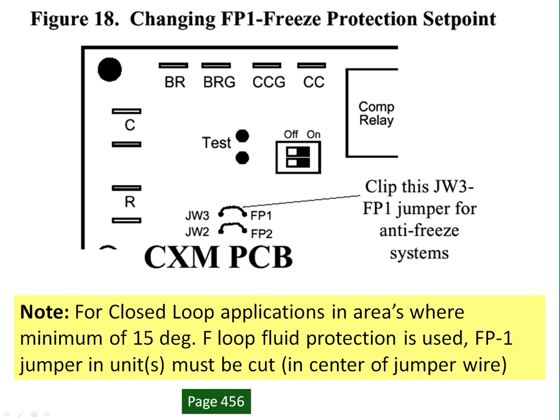So now you're good to go to cut that FP1 or JW3 jumper. What you want to do is make sure that when you cut that jumper, you separate those wires. I've seen guys just snip it, and yet the wires are close enough together they actually kind of remake contact. So make sure you separate them out a little bit, and please double check before and after you cut this jumper that you have cut the correct one. JW3, also known as FP1, is the jumper you wish to cut on that CXM board.